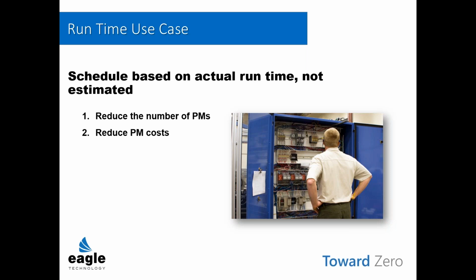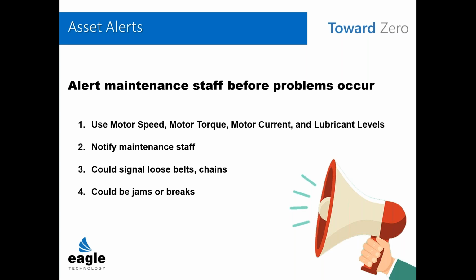And the savings there are pretty obvious. What that does is reduce the amount of time maintenance staff spend doing preventative maintenance. Instead of scheduling it once a month, let's say, maybe it's going to be scheduled every 38 days, because the machine or motor doesn't run as often as was estimated originally. That also cuts down on spare parts. So: less PMs, less hours spent, and less spare parts.